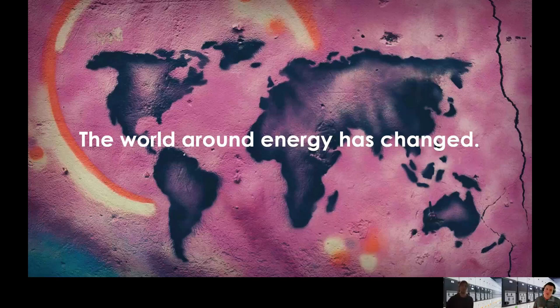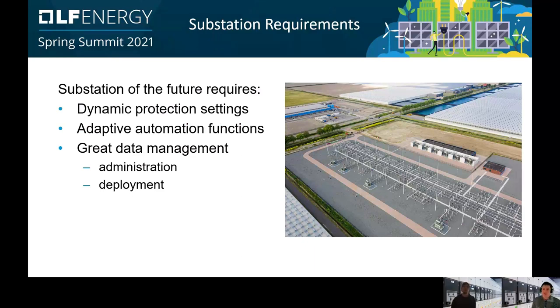And with these challenges, we as a DSO need to cope with these challenges, and that's why we're looking into substation automation as part of it. So if you look at substation automation in particular, we see a need of more dynamic protection settings. If you look at the load from a cable, for example, that can vary in time. And obviously you want to change your protection settings as well. So if it's cold weather, maybe the cable allows more distribution of energy. And if it's hot, there's not so much capacity.